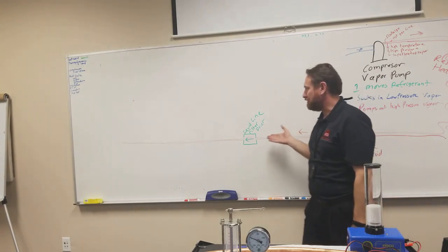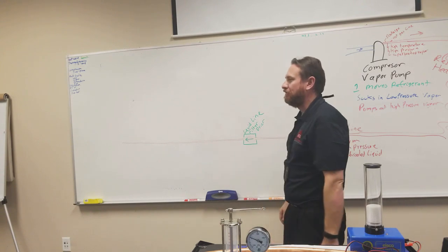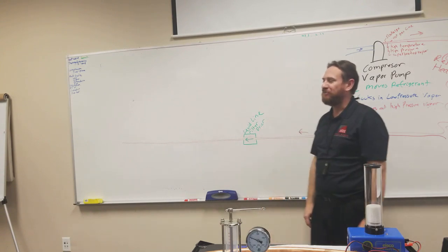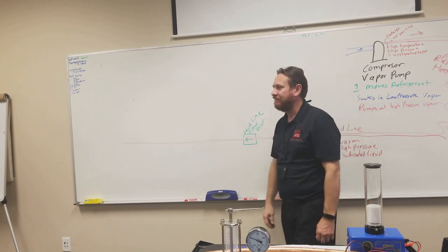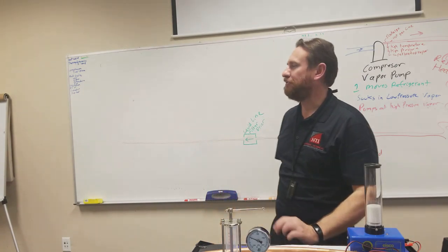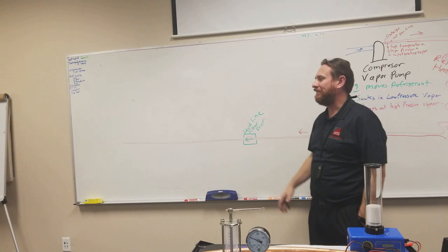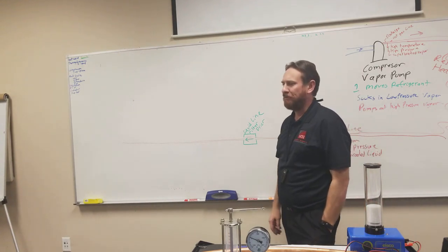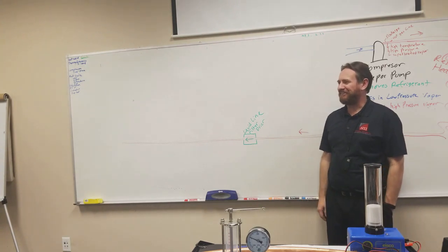That moisture, when you open these lines up, collects inside of these pipes, and you have to get as much of that out as possible. But you can't get it all out. So that last little bit that's left will collect in here. It's such a small amount that it can capture. You have to make sure when you're doing work on it, you get everything out that you can. A lot of people say, oh, just do whatever because that'll catch it all. It's not how it works.